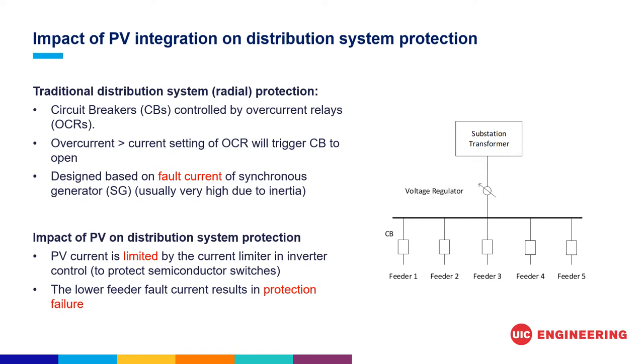However, the PV current is limited by the current limiter in the inverter control, which is used to protect the semiconductor switches of the inverter. This lower fault current on the feeder usually cannot be detected by the overcurrent relay, and thus results in protection failure.